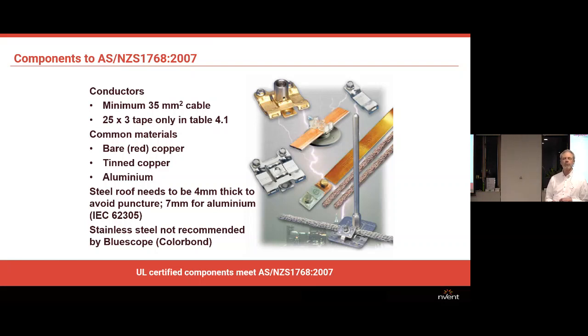The materials commonly used are bare copper, tin copper and aluminium. And that's an important consideration because of galvanic corrosion between the lightning protection components and the structure materials. So if you have a zinc aluminum roof, you'd go for aluminium. And if you've got a membrane roof, you could use probably whatever you like, but more likely tin copper or copper.